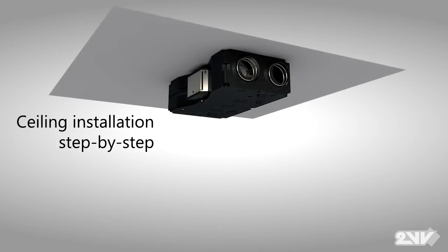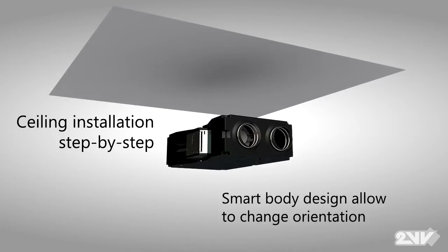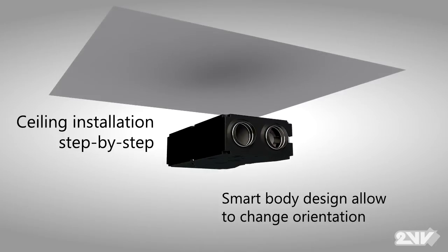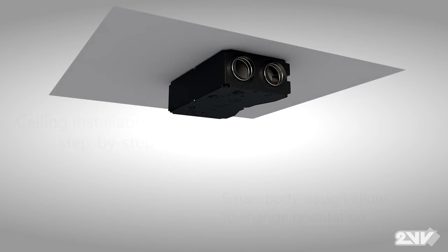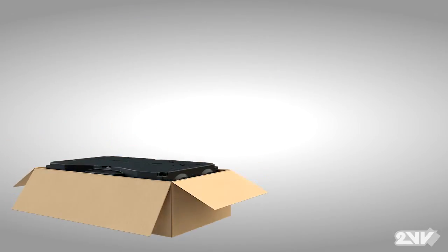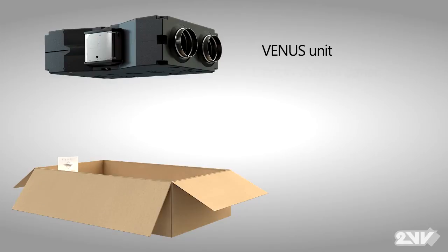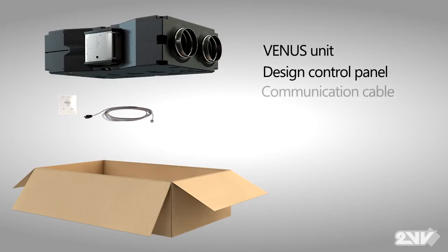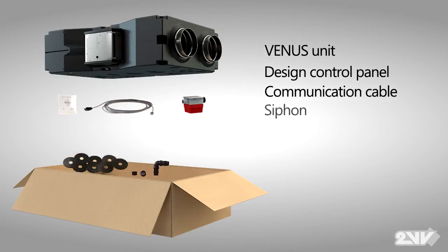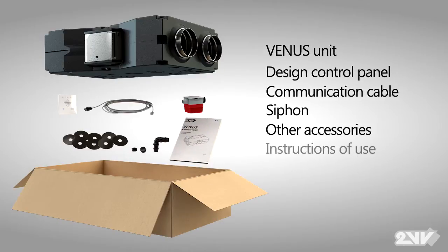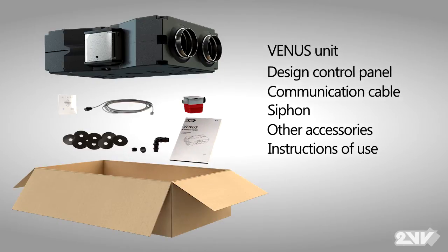When placing the unit, it must be installed in a horizontal position. The parts that are included with every VENUS heat recovery unit are as follows: VENUS unit, design control panel, communication cable, siphon for draining condensate, installation accessories, and instructions for use.